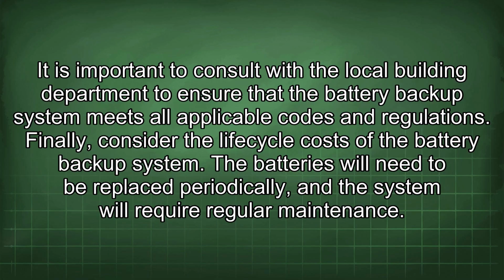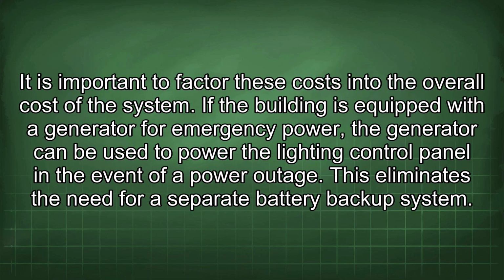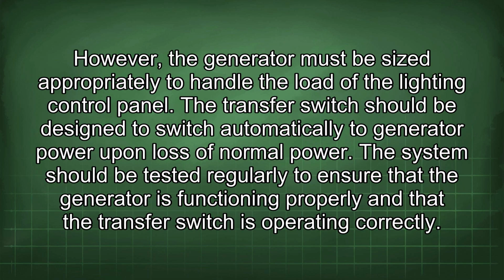The batteries will need to be replaced periodically, and the system will require regular maintenance. It is important to factor these costs into the overall cost of the system. If the building is equipped with a generator for emergency power, the generator can be used to power the lighting control panel in the event of a power outage. This eliminates the need for a separate battery backup system. However, the generator must be sized appropriately to handle the load of the lighting control panel. The transfer switch should be designed to switch automatically to generator power upon loss of normal power.